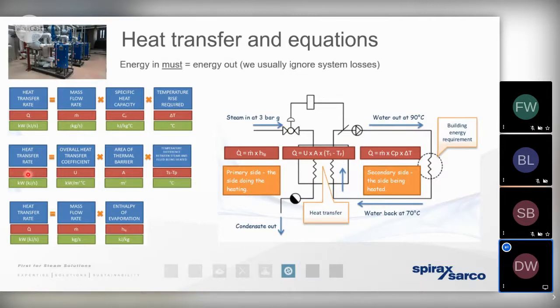And then finally, we can use the equation that you can see on the bottom of the screen here, or on the left-hand side of the process flow diagram. We can multiply the mass flow rate of the steam required by the heat exchanger by the latent heat energy, or the enthalpy of evaporation that's present in the steam. Again, we can get that from the steam tables, and that will tell us the amount of heat energy that is required on the primary side of the heat exchanger in order to satisfy the process.